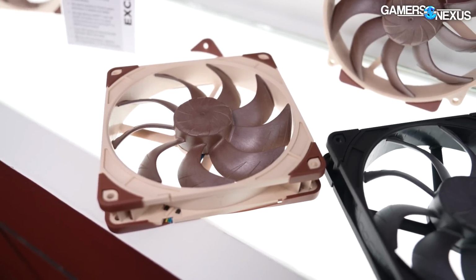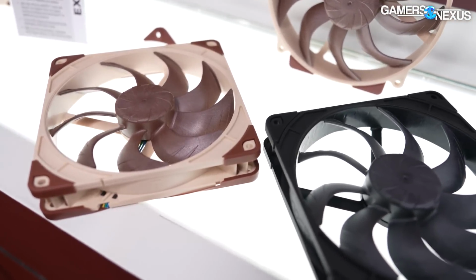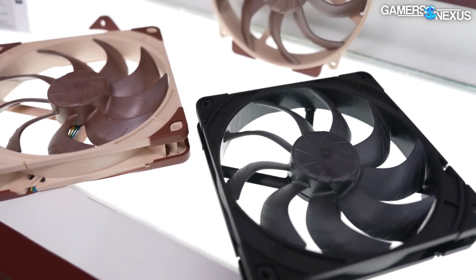One thing to keep in mind is that we still don't want you to torque the fans excessively. We advocate 0.2 Newton meter maximum torque, which may sound very low, but with your average radiator screw that amounts to a total compressive load on the entire fan of around 30 kilograms. It's not that the fan is fragile, it's that it's quite easy to apply a lot of force with screws, especially since some screw heads are very small, giving very little friction between the screw head and the fan frame. Also, lubricants are sometimes used to prevent the black paint from wearing too quickly, and those lubricants also reduce the friction between the screw head and the fan frame.